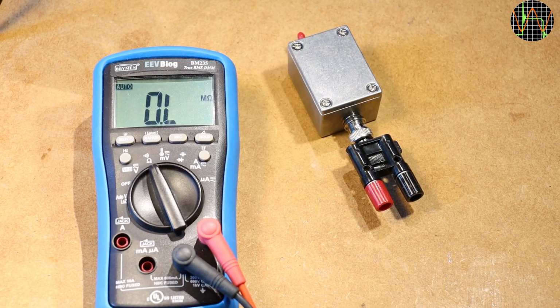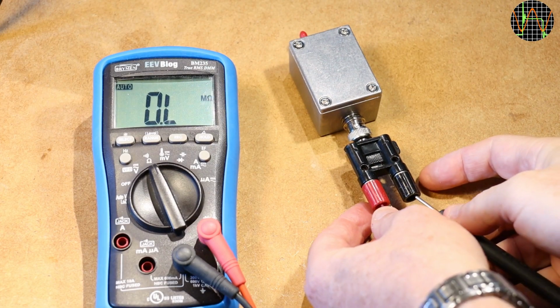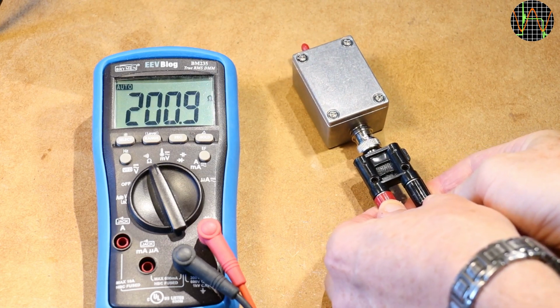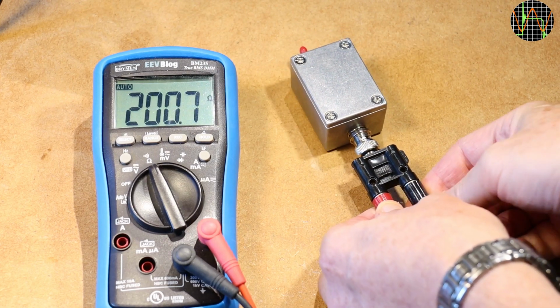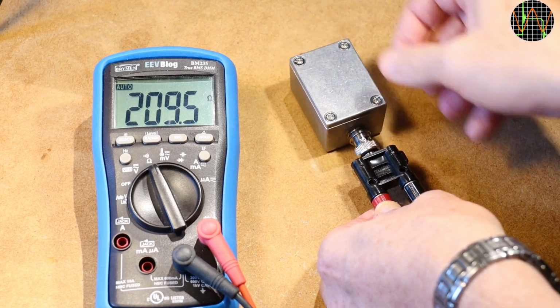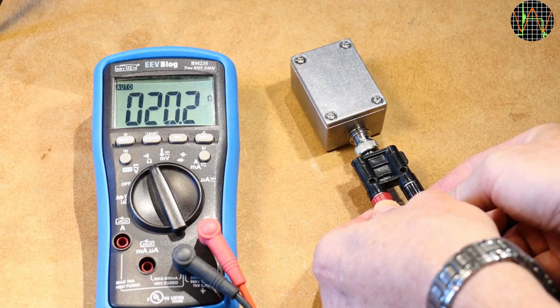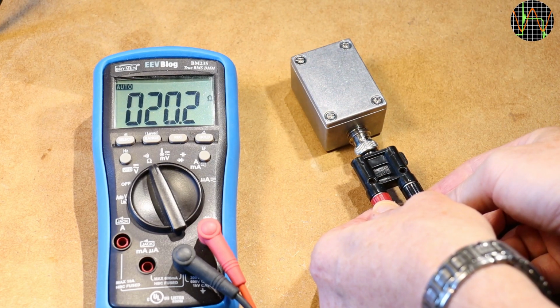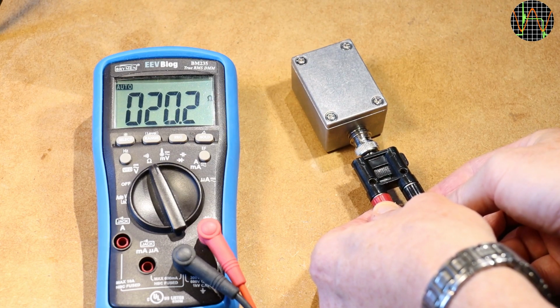A simple way to test the wiring for correctness is to check the resistance on the output with no current transformer connected. It should be 200 ohms or 20 ohms depending on the switch. The small deviation is due to not using rel mode to null the leads before measuring.